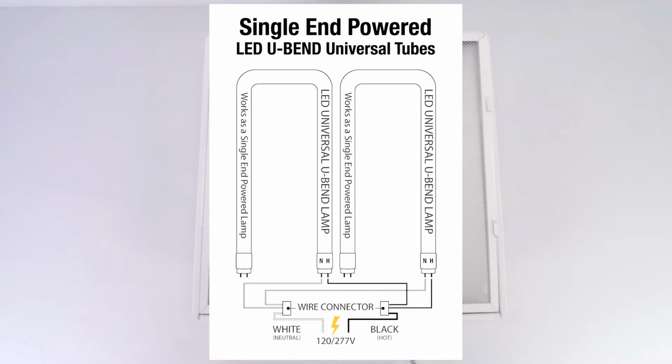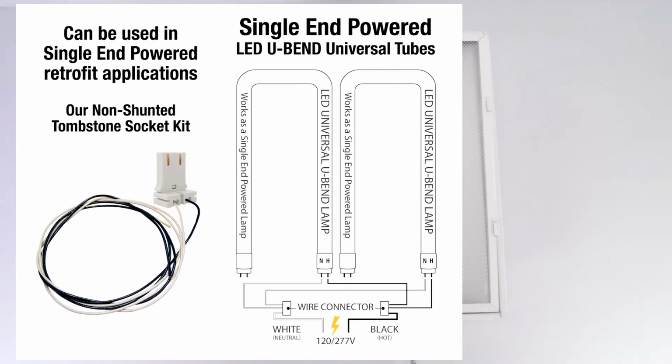Second, the drawing for single end fed LED retrofit tubes. And you can see it uses a non-shunted tombstone or socket, and hot is on one side and neutral on the other. And here's a little drawing that kind of shows how that one works. That can be found on our website also.